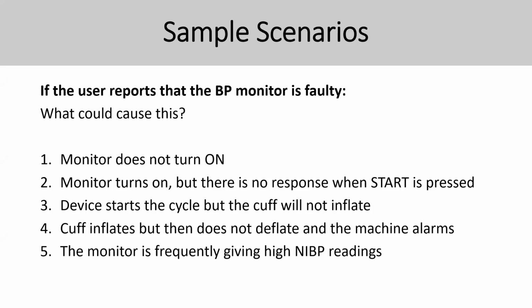Let me answer the question for number 4. Yes, number 4 is because the cuff is leaking. When the cuff is leaking, the pump motor will try to pump and pump to reach the target, and the cuff is still leaking, so it will be an error. And number 5 is the cuff size.